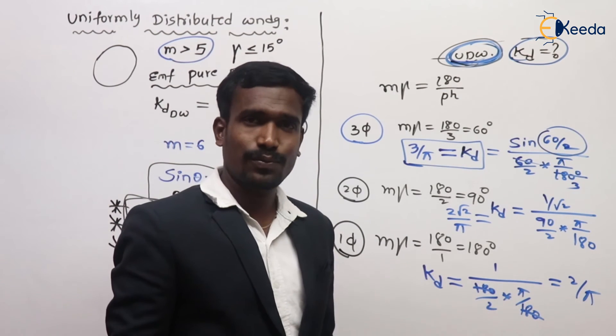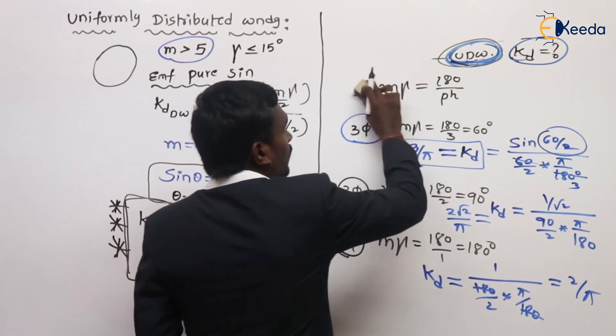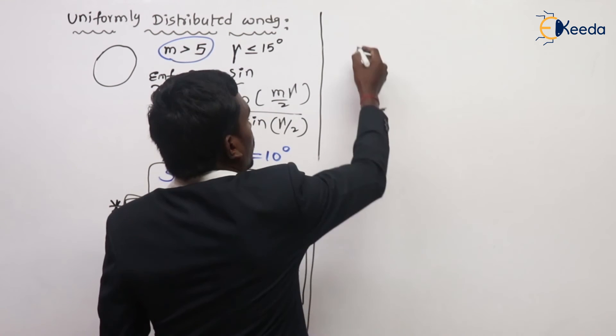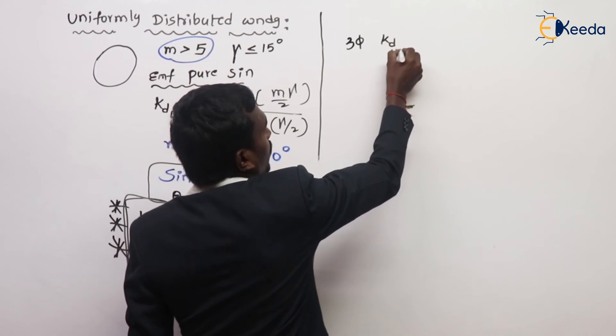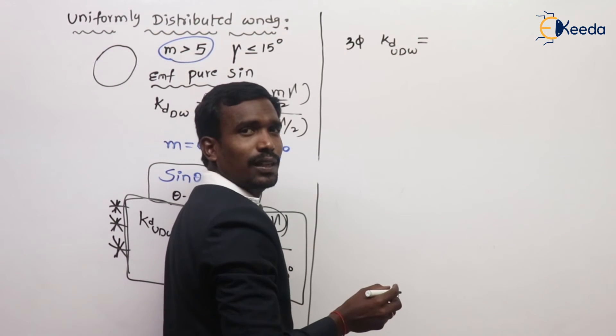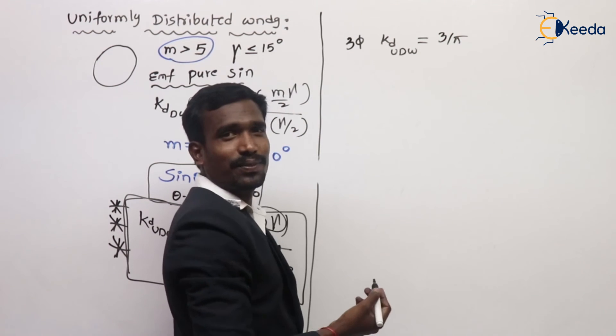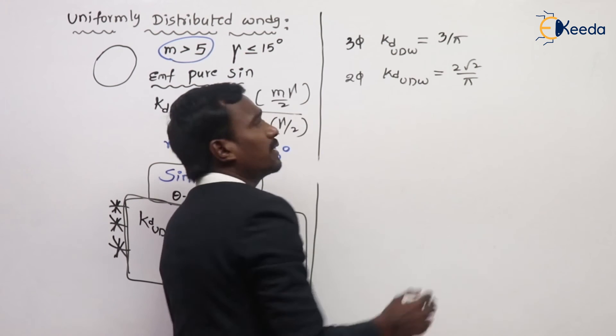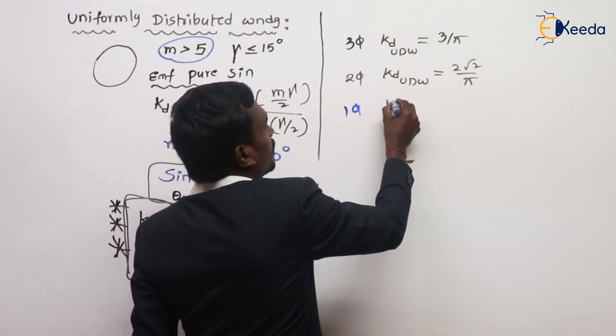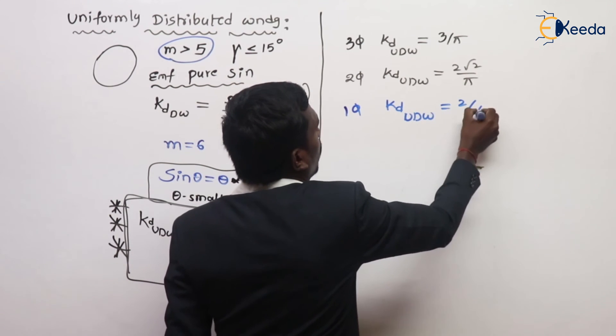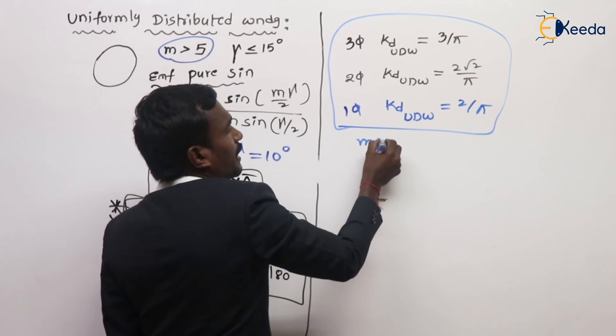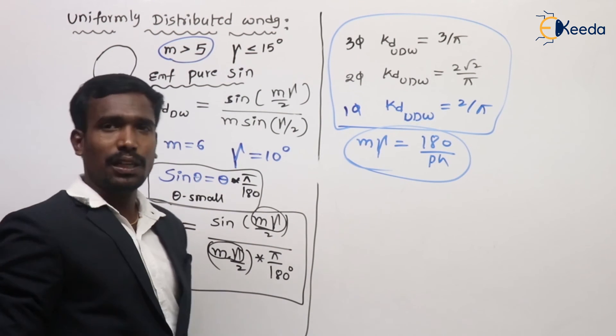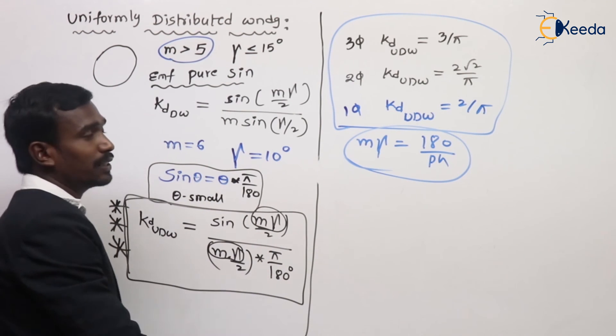In conclusion, for uniformly distributed winding: the distribution factor for a 3-phase machine is 3/π; for a 2-phase machine it is 2√2/π; and for a single-phase machine it is 2/π. This is because mγ = 180/number of phases. From this, we can calculate directly without needing the full formula.